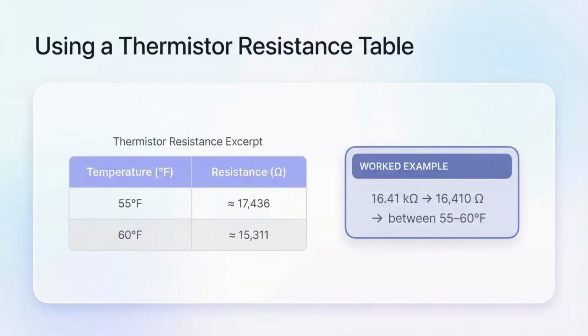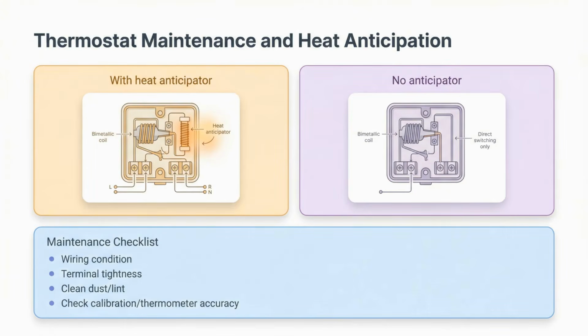To use a thermistor table, convert the meter reading properly. If the meter is on kiloohms and reads 16.41, that's 16,410 ohms. Then compare it to the resistance table to estimate temperature. In this example, it lands between 55 and 60 degrees Fahrenheit. Room thermostats need little maintenance, but they should be checked before heating season. The module emphasizes not using a thermostat with a heat anticipator for hot water systems. Anticipators are meant for forced air and can shut the boiler off early. Service is mostly inspection, wiring condition, tight terminals, clean sensing elements, and confirm calibration accuracy.